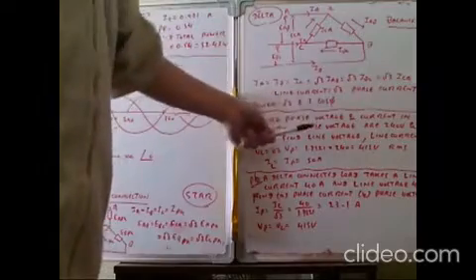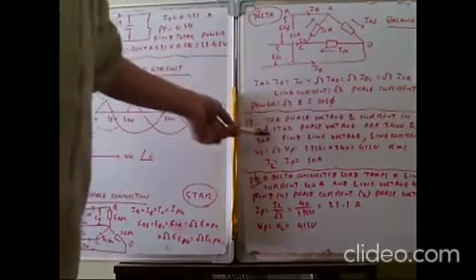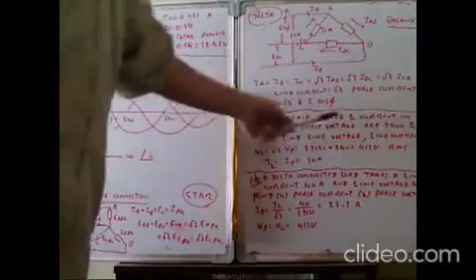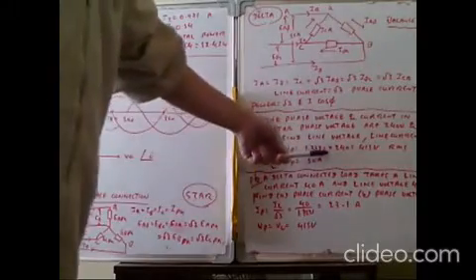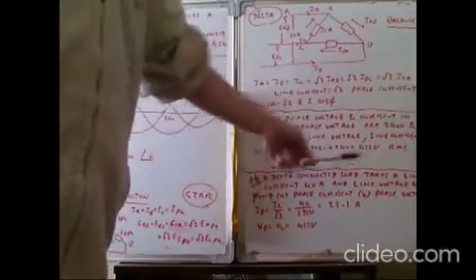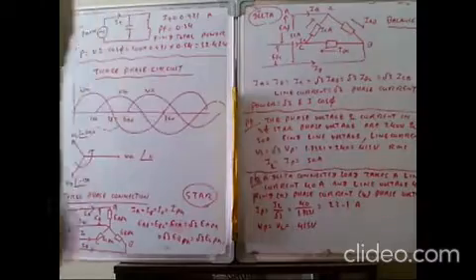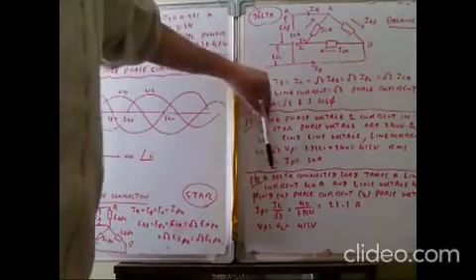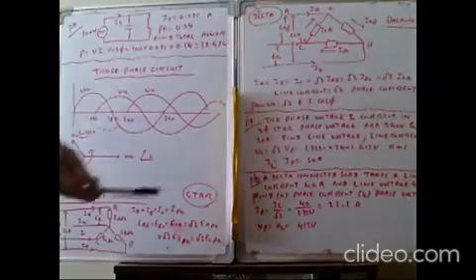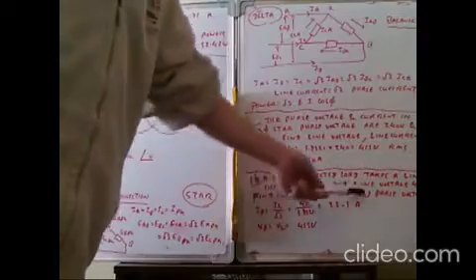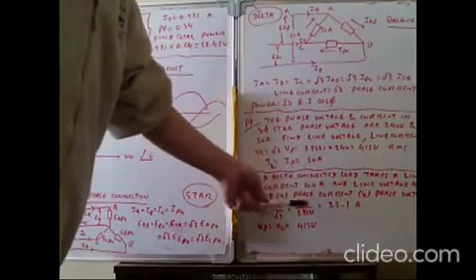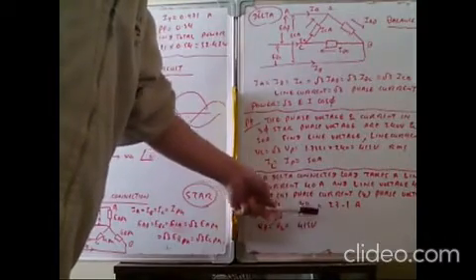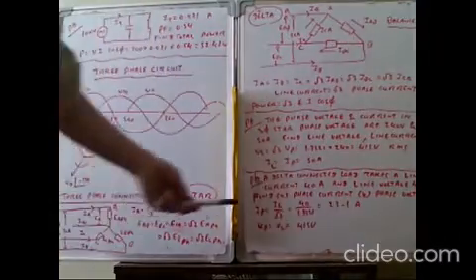Example: In a three-phase star connection, phase voltage is 240 V and current is 50 A. Find line voltage and line current. Line voltage = √3 × phase voltage = 1.732 × 240 = 415 V. Line current equals phase current = 50 A. Another problem: delta-connected load, line current 40 A, line voltage 415 V. Phase current = line current / √3 = 40 / 1.732 = 23.1 A. Phase voltage equals line voltage = 415 V.